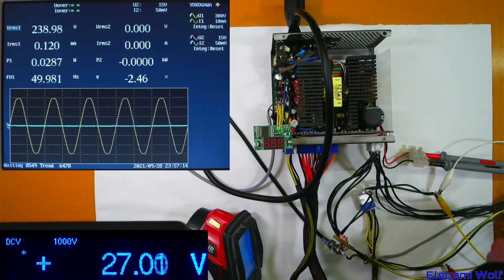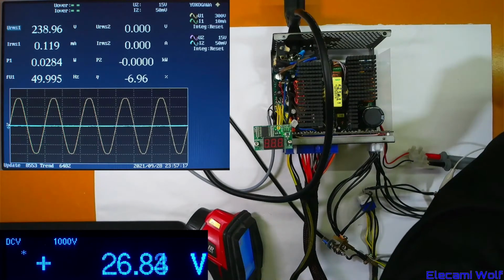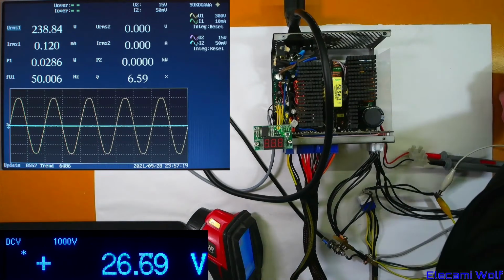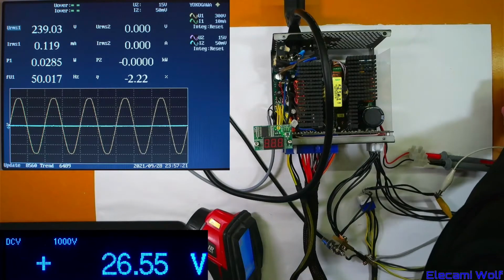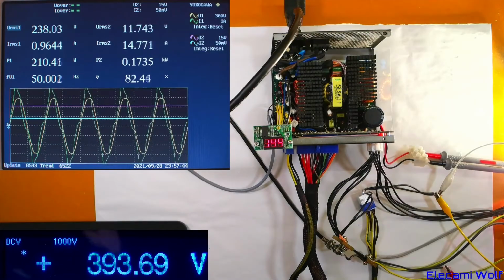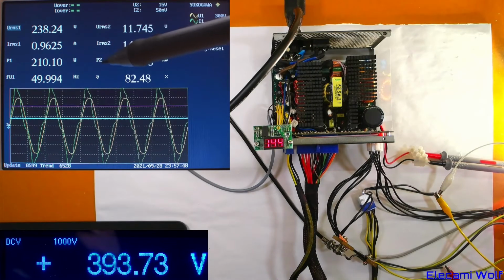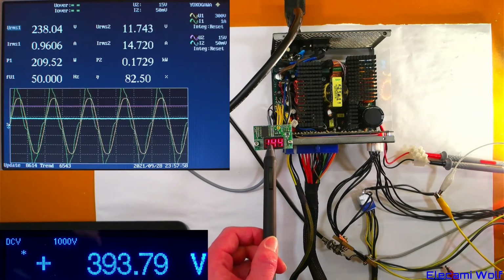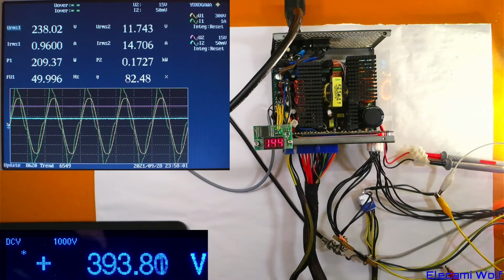We'll test one more time with a lower load level and see how the power meter correlates with the actual power consumption. 170 watts on the output, 210 watts on the input. The power meter there is closer to what the output load is, but it's still not particularly accurate. Seems like it's good to within about 100 watts. Wouldn't want to trust it any more than that.